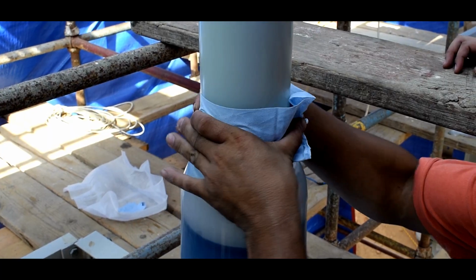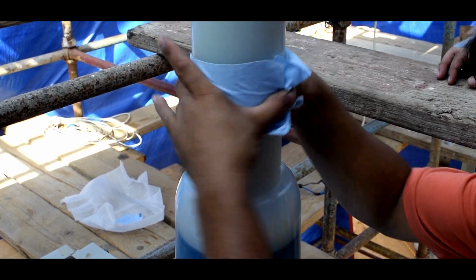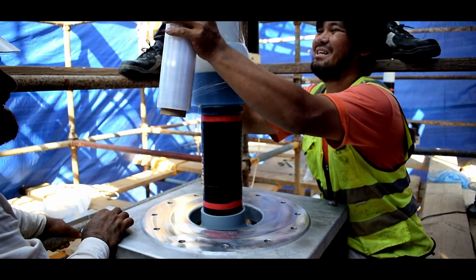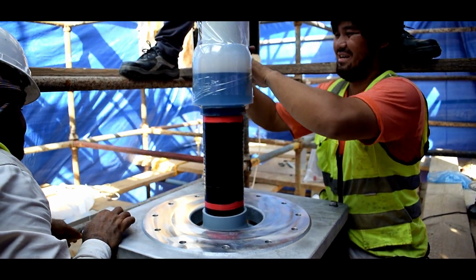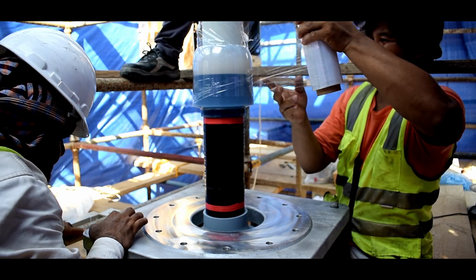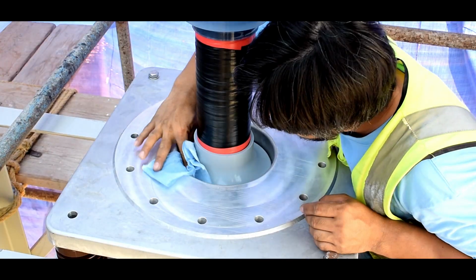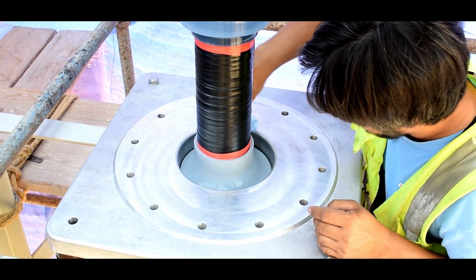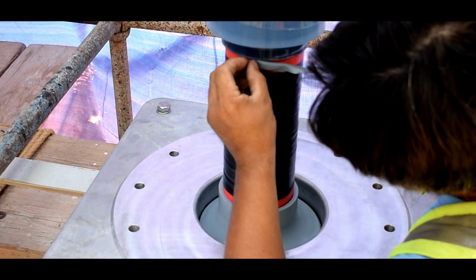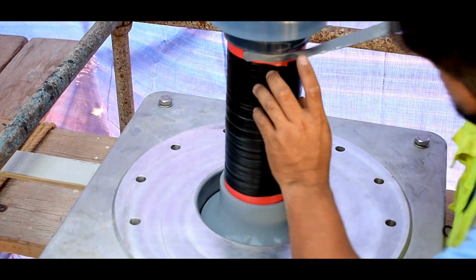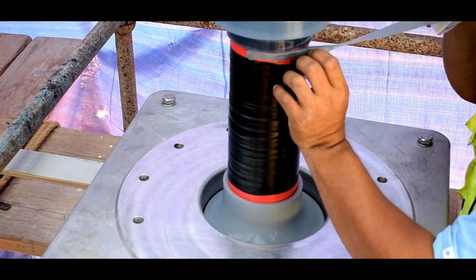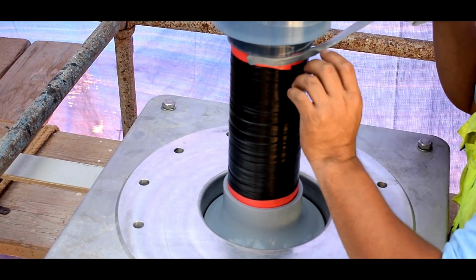The area above the stress cone and between the stress cone and screen pot is degreased by cleaning 2 to 3 times with acetone. Sealing tape is wrapped between the stress cone and insulation screen, so that half goes around the stress cone and half goes over the insulation screen.